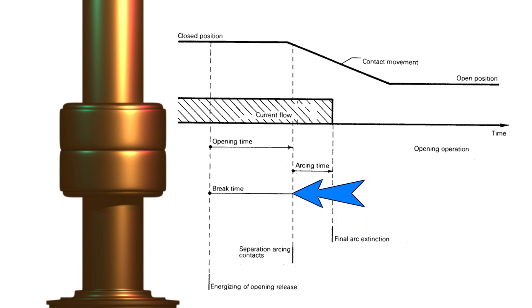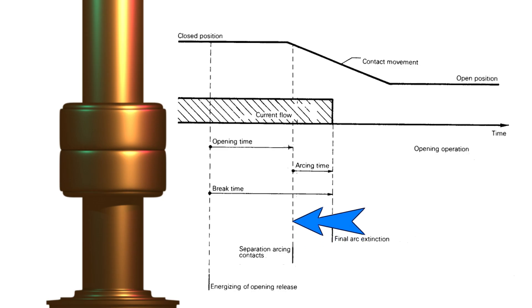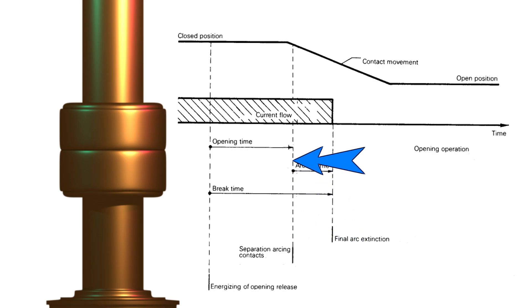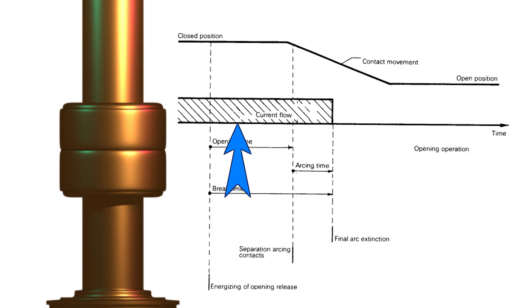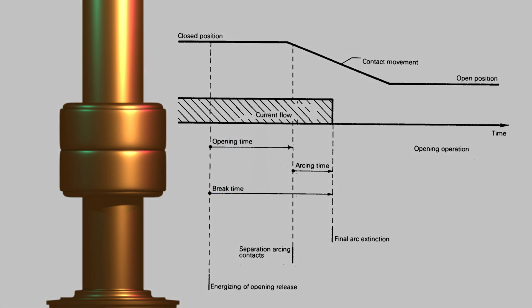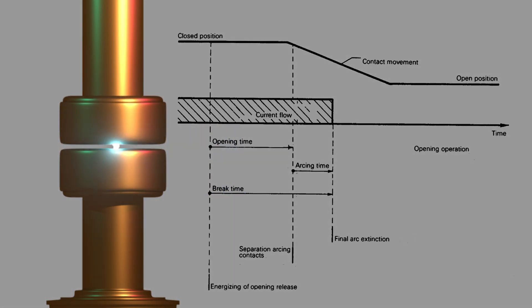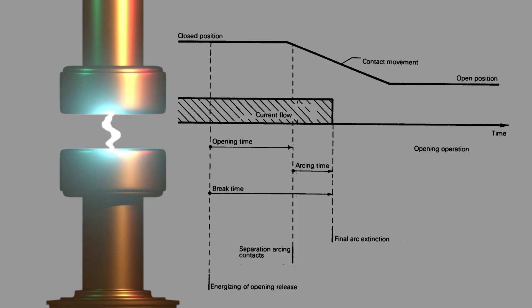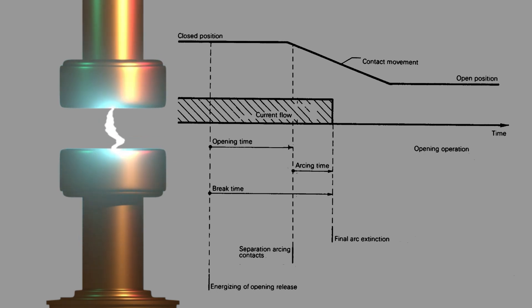The time required to actuate the moving contact after energization of the opening release cannot be avoided due to the linear and rotational movement of different parts of the mechanism. At this point, say this is the instant when the moving contact gets finally separated from the fixed contact — physically and finally separated. After physical separation of the contact, there will still be arcing that continues to sustain the current through the contact. So current cannot be physically interrupted immediately after physical separation of the contact.